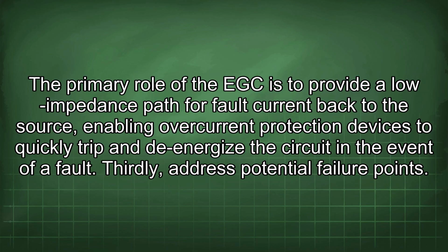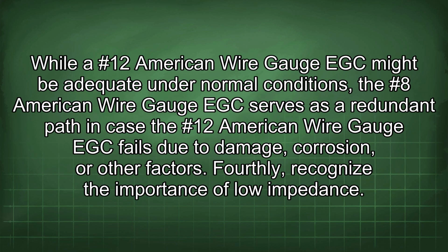The primary role of the EGC is to provide a low-impedance path for fault current back to the source, enabling overcurrent protection devices to quickly trip and de-energize the circuit in the event of a fault. Thirdly, address potential failure points. While the #12 American wire gauge EGC might be adequate under normal conditions, the #8 American wire gauge EGC serves as a redundant path in case the #12 American wire gauge EGC fails due to damage, corrosion, or other factors.